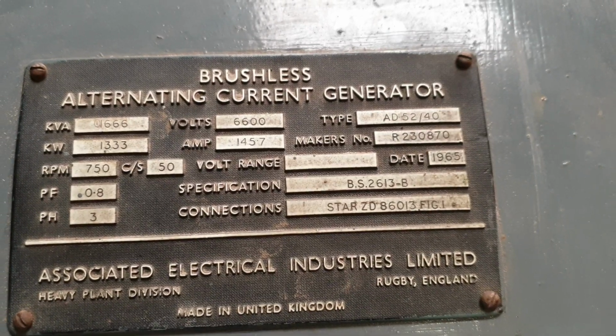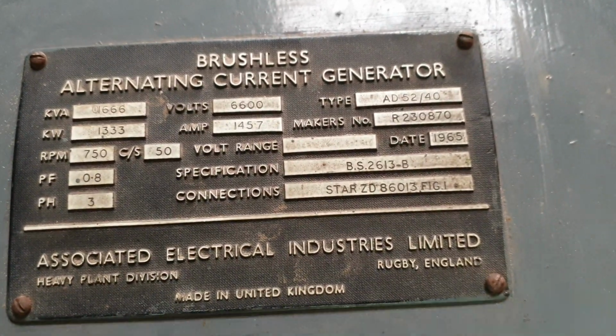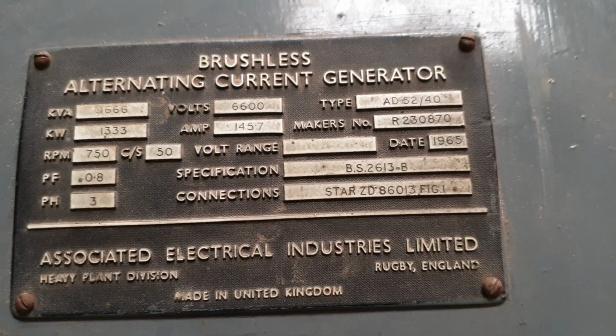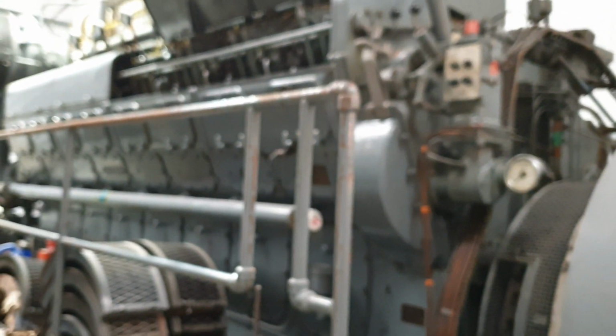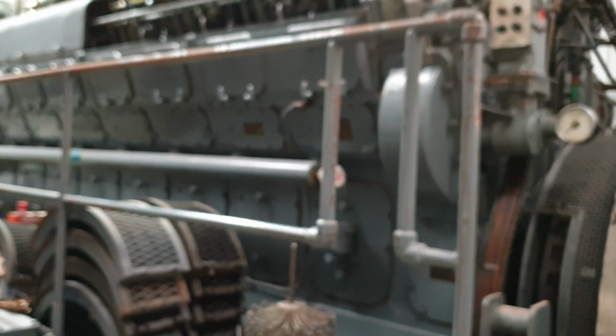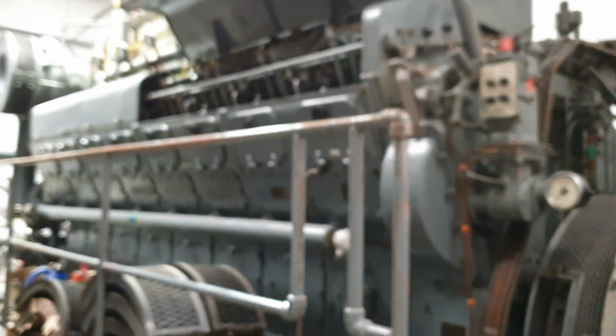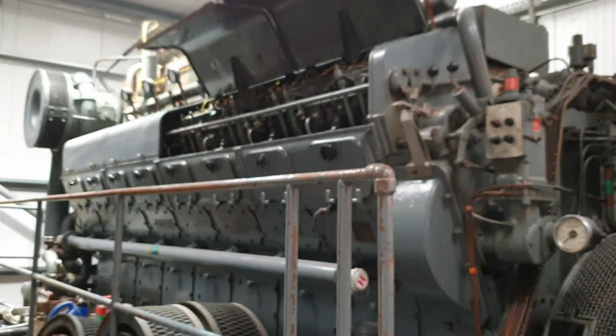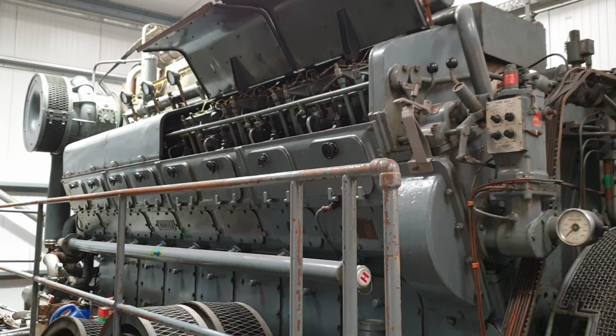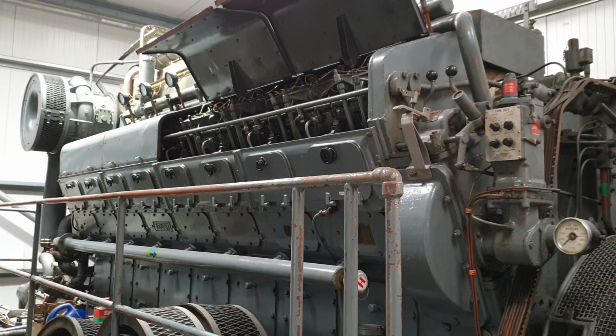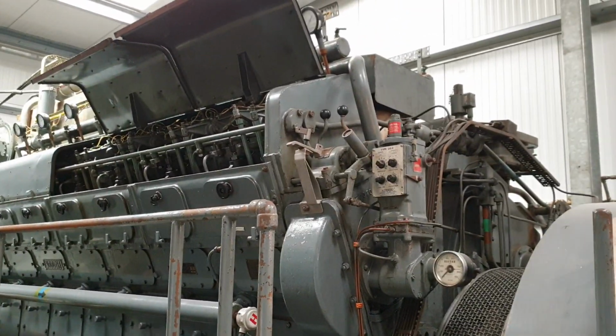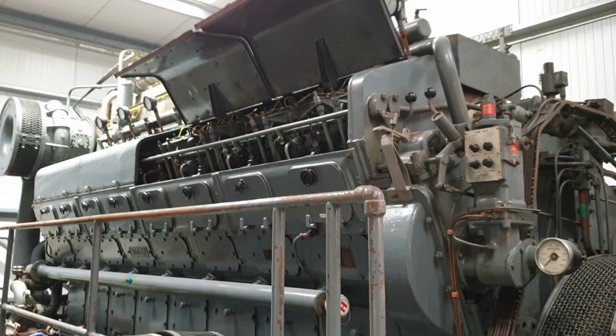750 RPM, basically classed as a mid-speed running generator, this is. Because anything below, I think it's 300 RPM, is classed as a low RPM generator, low speed. And this is classed as mid-speed. Anything over 1000 RPM would be classed as something like high speed. So this is a medium speed generator.